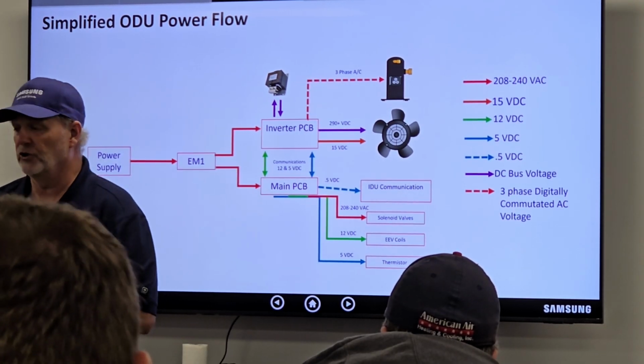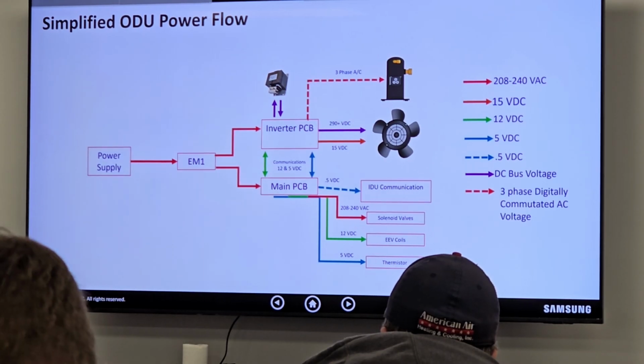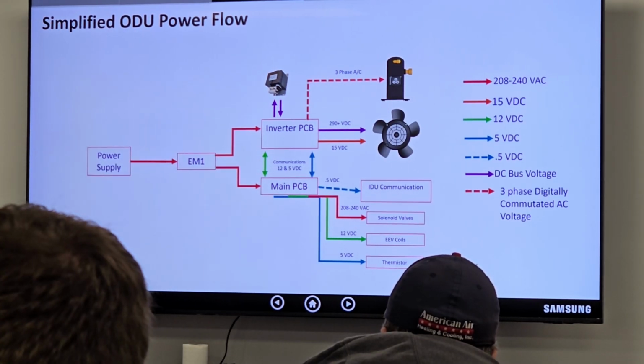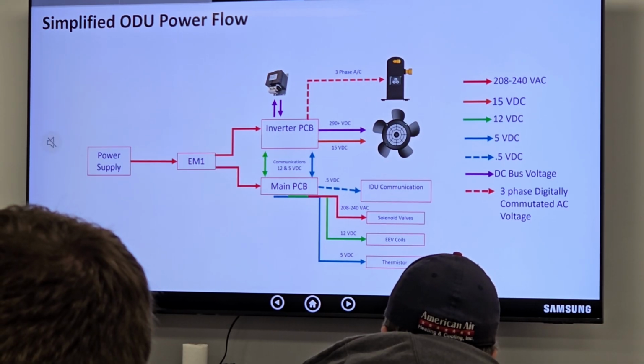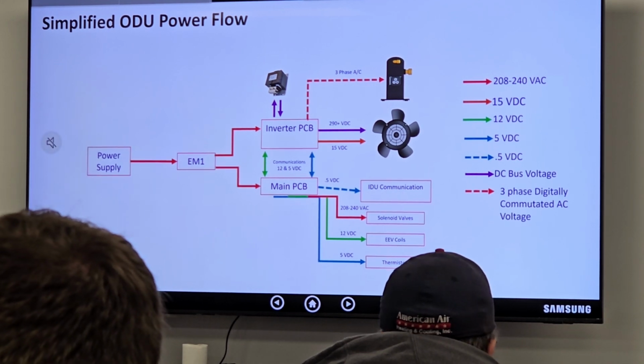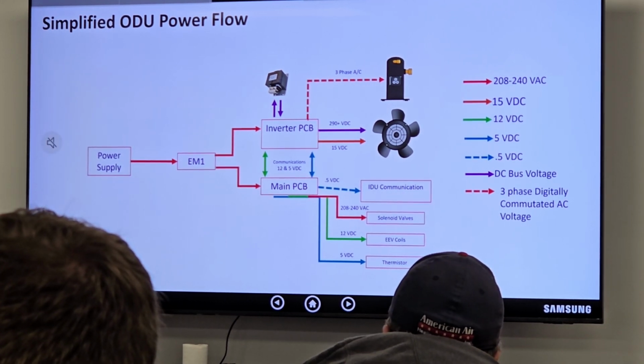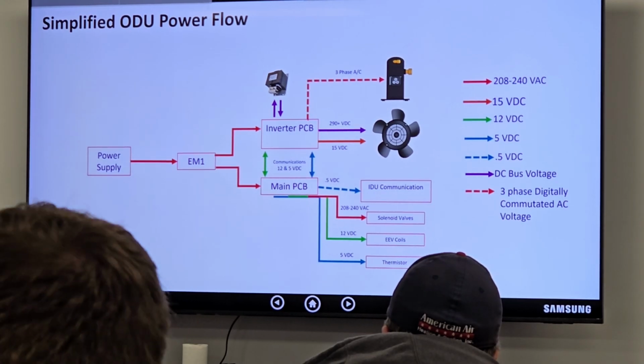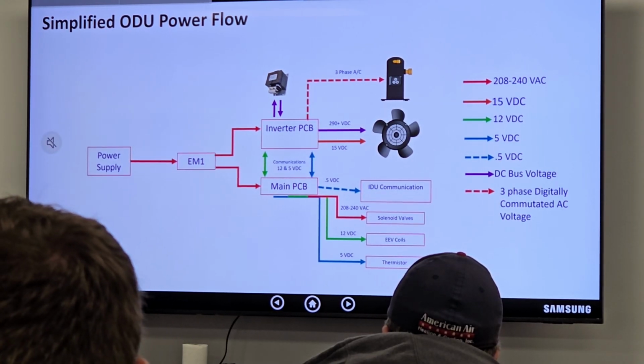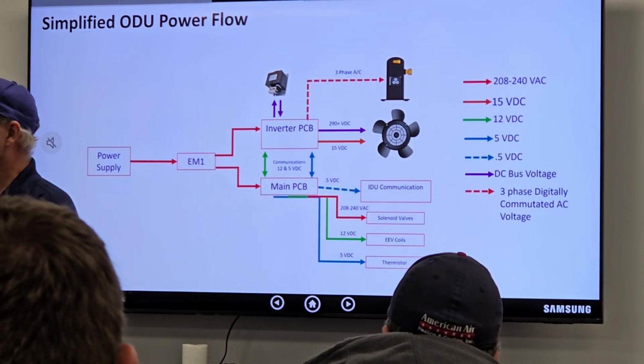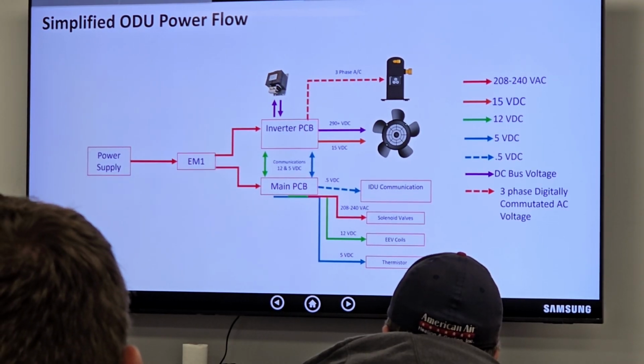Now here's the kicker to a shielded cable. Where do you hook the shield up? Only on one end. And that end is at the outdoor unit. Think of the shield as a drain. If I have current coming onto that shield, where do I want to send it? I want to send it to the outdoor unit, get it out of the system completely. If I hook the shield up on both ends, indoor and outdoor, what happens if I do get a drain onto the shield? It doesn't go anywhere. It has nowhere to bleed off. It's back and forth.